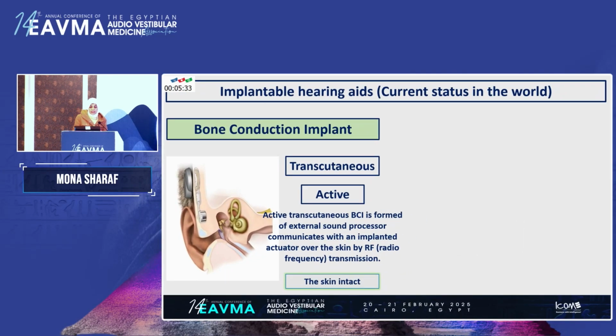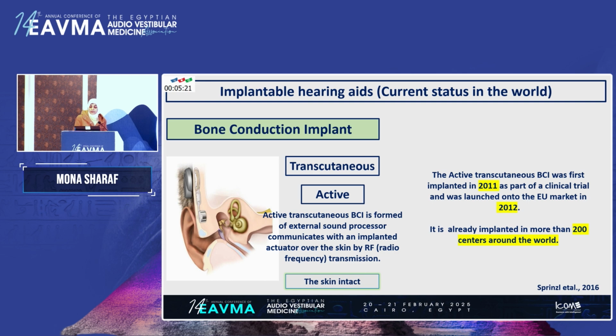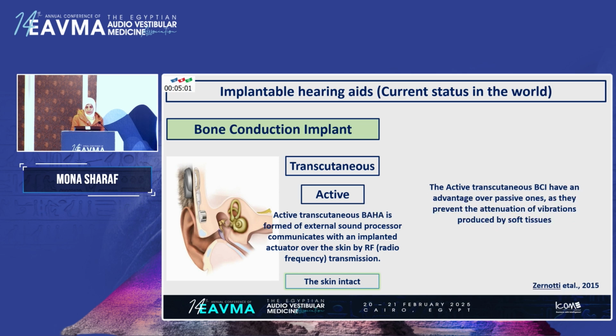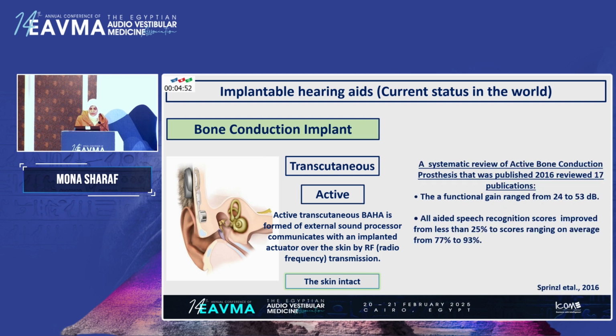The active transcutaneous bone conduction implant is formed of an external sound processor that communicates with an implanted actuator over the skin by radio frequency transmission. It was first implanted in 2011 as part of a clinical trial, and approved in the European market in 2012. It is already implanted in more than 200 centers around the world. It has the advantage over the passive one as it prevents the attenuation of vibration caused by soft tissue.